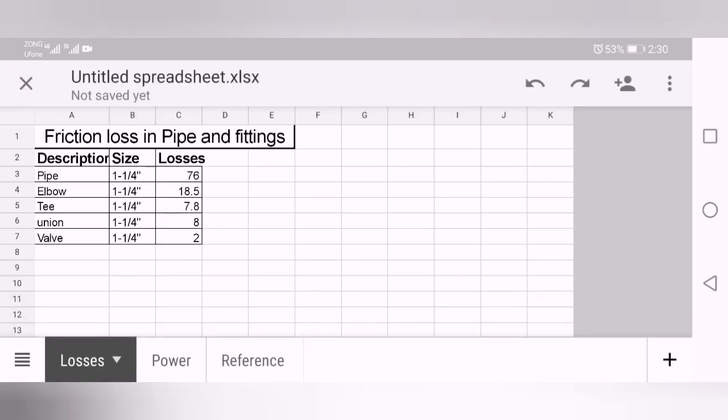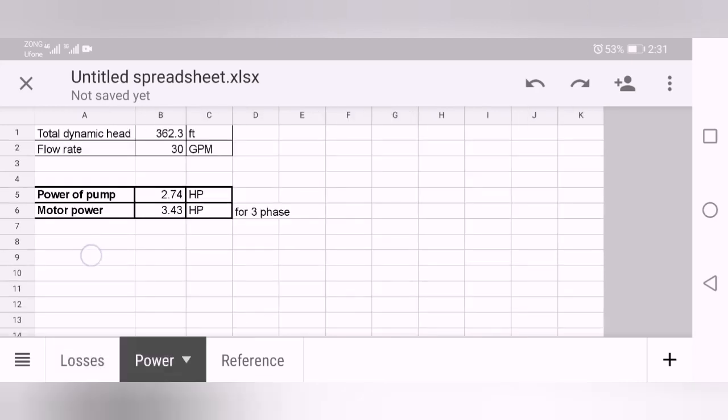Add this total losses with the static loss, like building height is 12 feet, 20 feet, 100 feet. So add both of them, you will get the static head. Adding both of these, static head and the fitting losses, you will get the total dynamic head. Here you can see the total dynamic head in my case is 362.3 feet. All these losses are in feet and I needed 30 gallons per minute of flow rate.